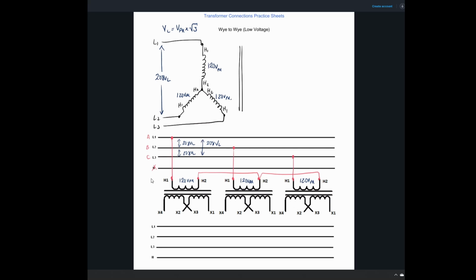So remember that the ratio here is 1.73 to 1. That's the ratio of the primary conductors to the secondary conductors. So with this guy, normally on all the other videos, we had 208 on the line and 208 on the phase, right? Because we're dealing with deltas on the primary. But now we've got 120 volts on the phase. So if I take 120 and I divide it by 1.732, that gives me 69 volts on the secondary.